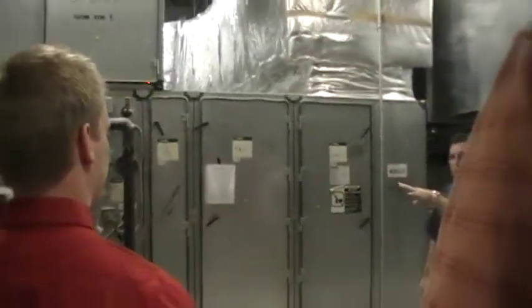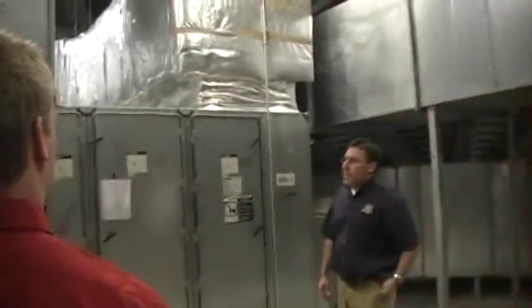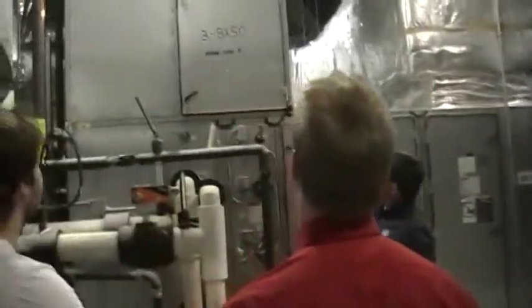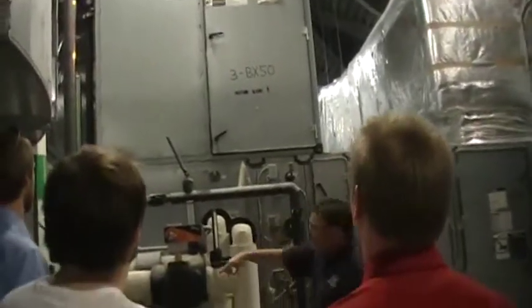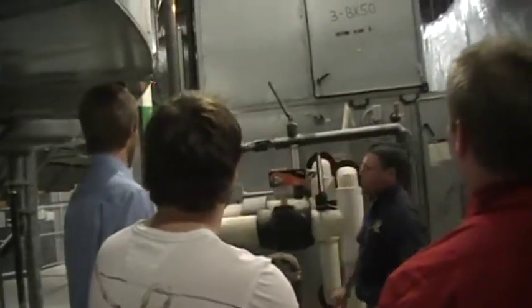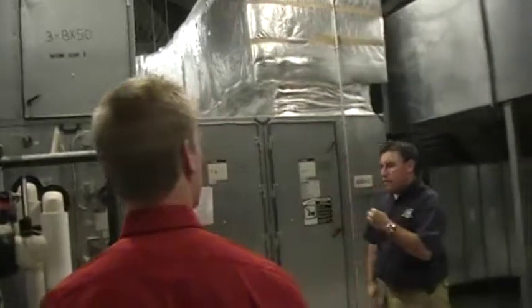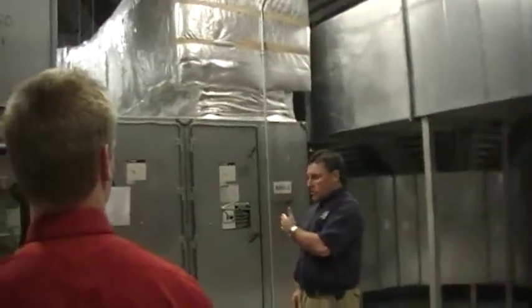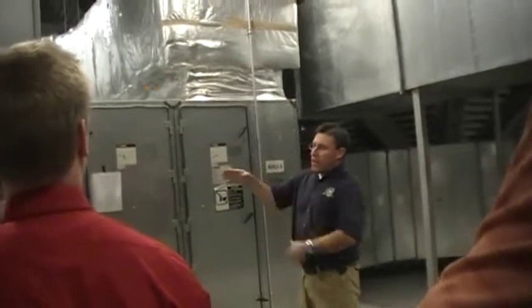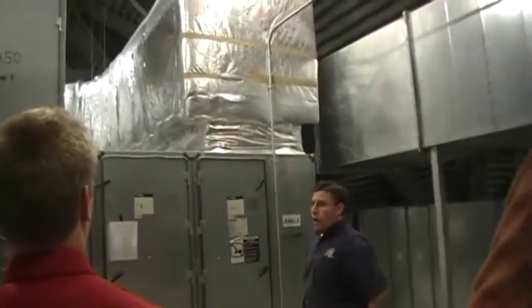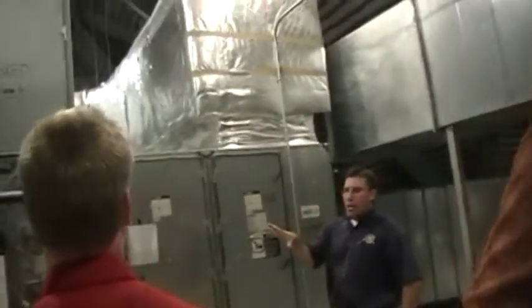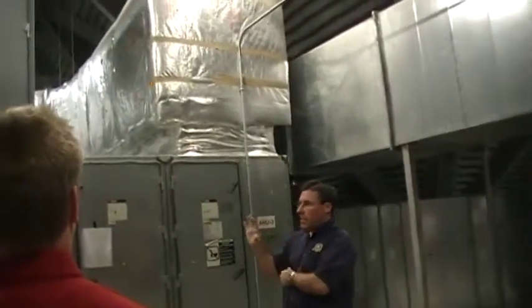This is what feeds each individual floor. This air handler right here serves the third floor, west end. Downstairs where we were talking, the variable air volume boxes. Somebody was asking where the fan is. The fan is actually right here in this section. It's got a variable speed drive on it, and so as it warms up during the day, those boxes open up. It's got a variable speed drive that senses the differential pressure in the ductwork, and it speeds the fan up. And at night, when those boxes close off, it slows the fan down.